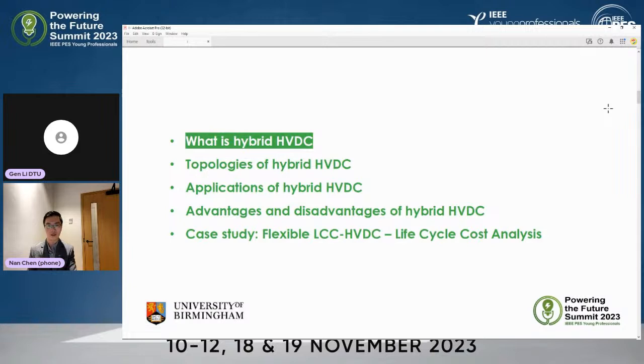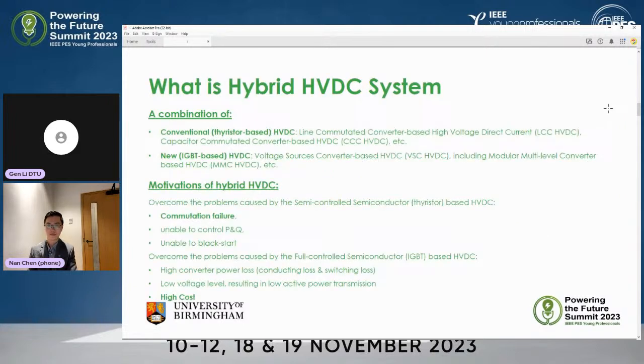So firstly, we'll talk about what hybrid HVDC is. It can be regarded as a combination of conventional HVDC, which is thyristor-based — for example, line commutated converter-based HVDC, shortened as LCC HVDC, and also capacitor commutated converter-based HVDC, CCC HVDC — and new HVDC, which is IGBT-based HVDC. It has other names, such as HVDC Light or HVDC Plus, depending on the producer. It includes voltage source converter-based HVDC, VSC HVDC, and MMC HVDC, standing for modular multi-level converter-based HVDC.